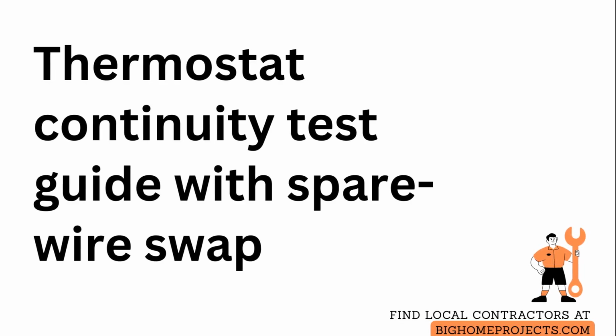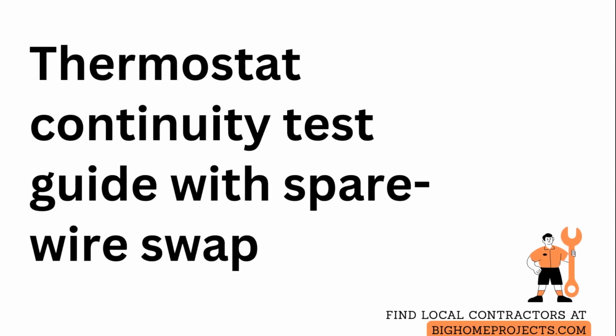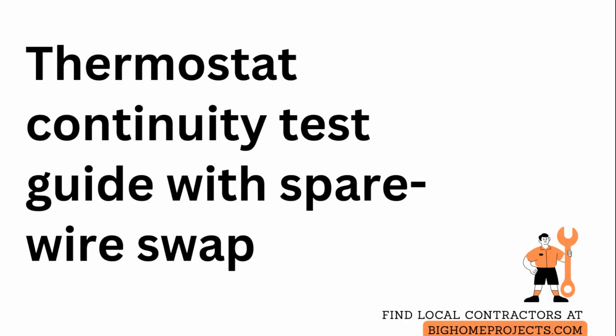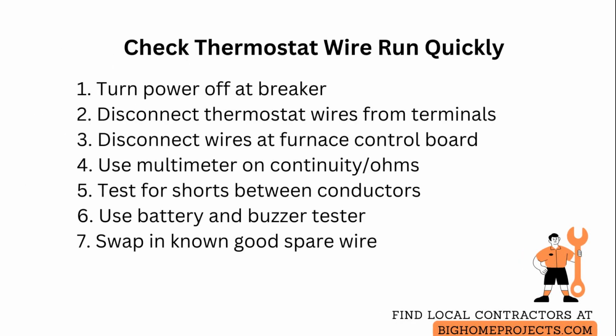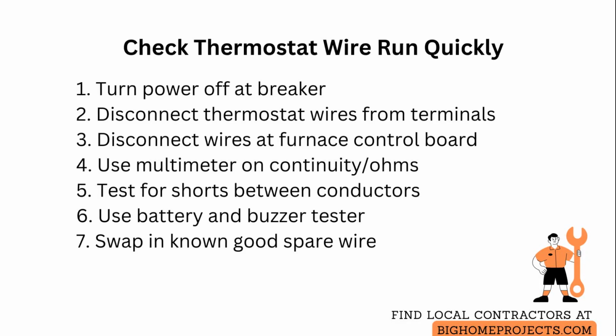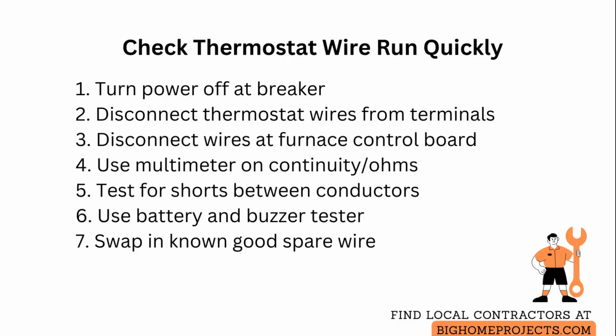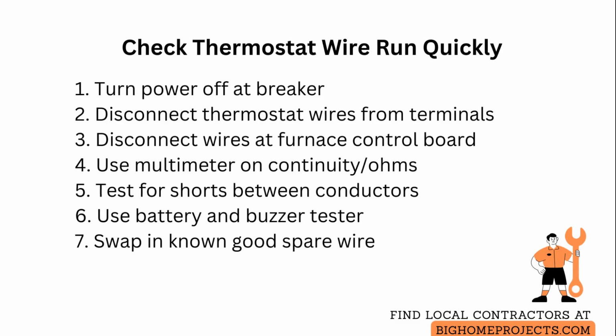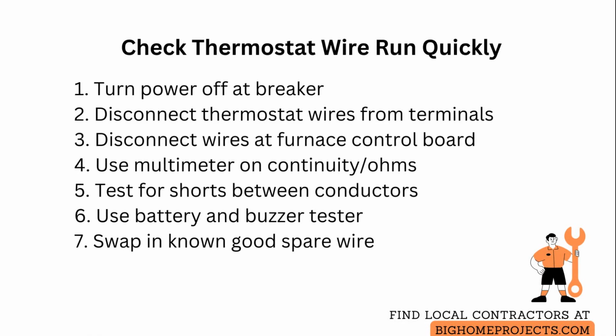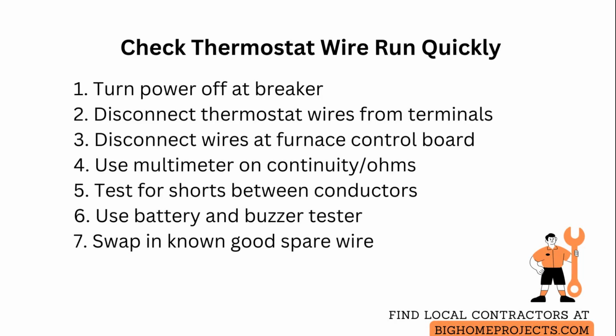Check the thermostat wire run between the thermostat and furnace by isolating and testing the conductors directly. Begin by turning power off to the heating and cooling system at the breaker to prevent damage or false readings. At the thermostat end, remove the cover and disconnect the wires from the terminal block so they are isolated. At the furnace or air handler, disconnect the same wires at the control board or terminal strip so both ends are free and not connected to equipment.